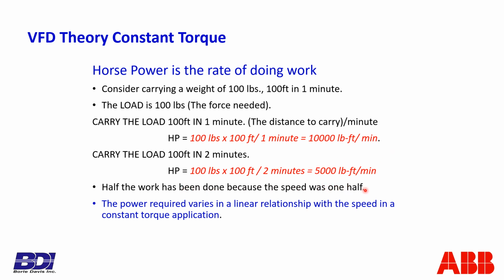This is the beauty of the variable frequency drive and the constant torque application. The full power is only needed at the fastest speed the engineer designs the system for. At all speeds below full speed, the power required drops off linearly with the speed, just as we saw, because we're slowing down. We're carrying the same load, but we're taking longer to carry it the same distance. We're doing less work each time. That is the beauty of how a constant torque load works. And that, we're going to see, is the beauty of what a variable frequency drive can deliver.